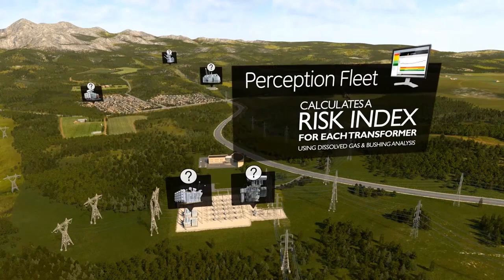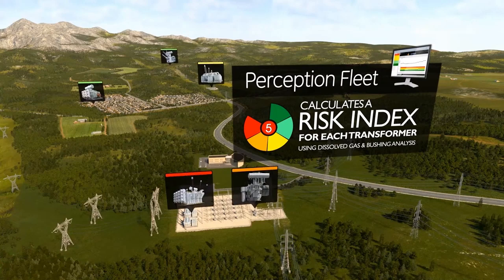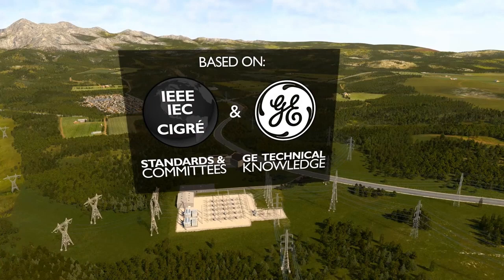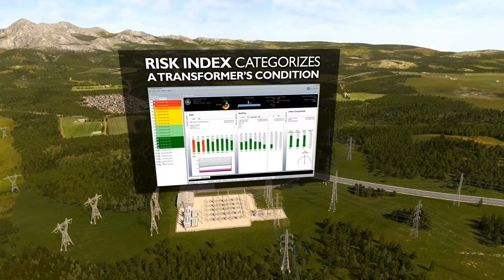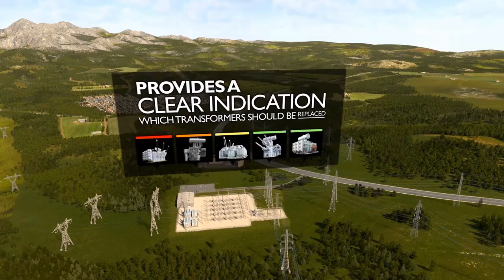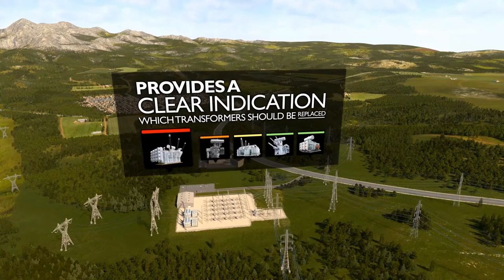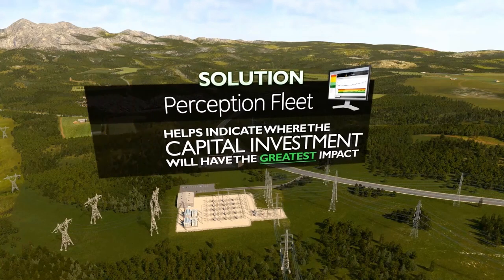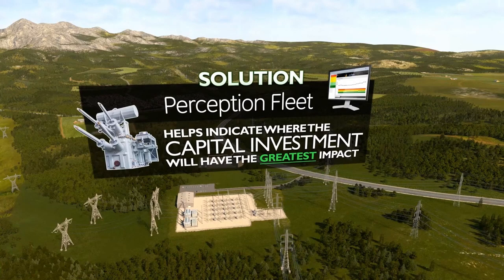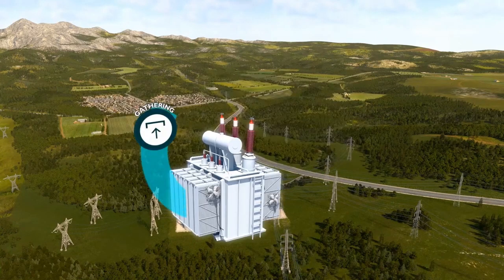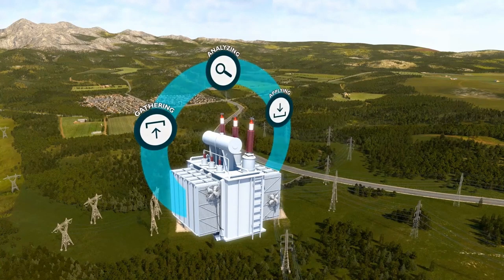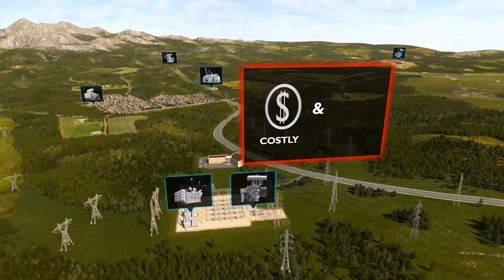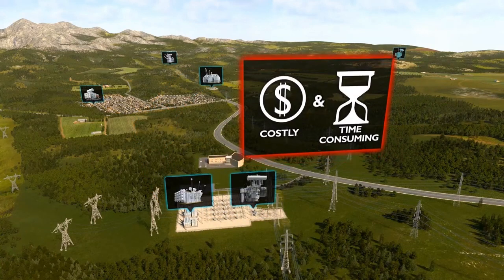Perception Fleet solves this challenge by calculating a risk index for each transformer in the fleet using dissolved gases and bushing analysis. Based on international standards, committees, and GE technical knowledge, the risk index categorizes a transformer's condition and provides a clear indication of which transformers in the fleet should be replaced and where the capital investment will have the greatest impact.